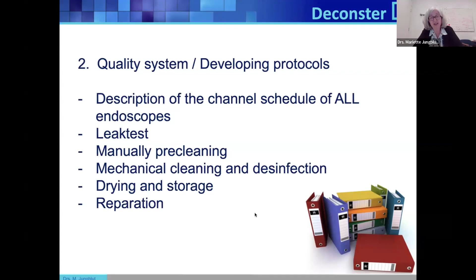Manual pre-cleaning directly after use, as soon as possible, after 5 minutes, after 20 minutes, but certainly not after 2 hours. If that happens, we need a protocol for how to deal with it. Extensive soaking, it has to be in a protocol. Mechanical cleaning, disinfection, drying, storage, and then last but not least, again, the repair. Scopes are very difficult devices, they will break down.